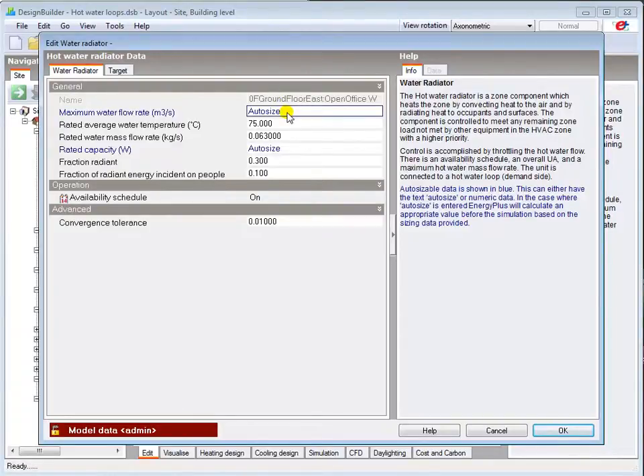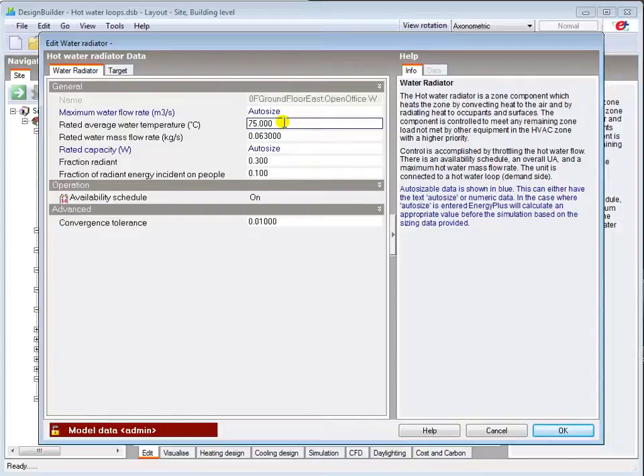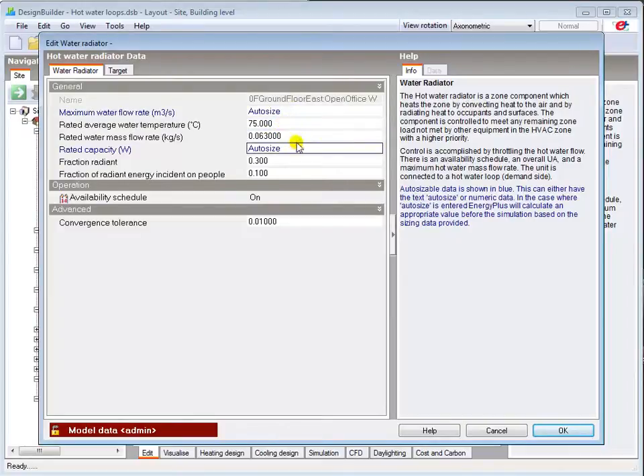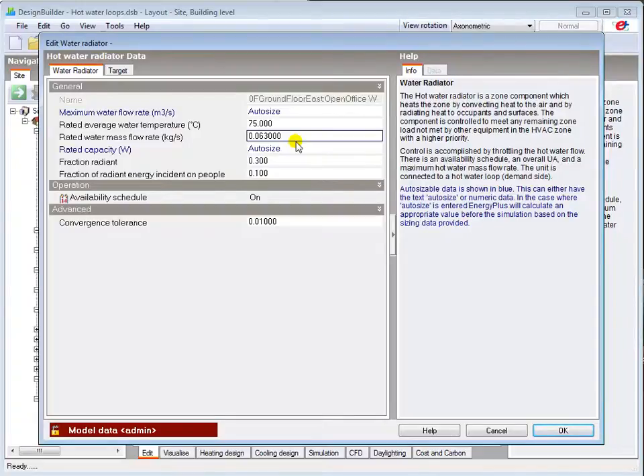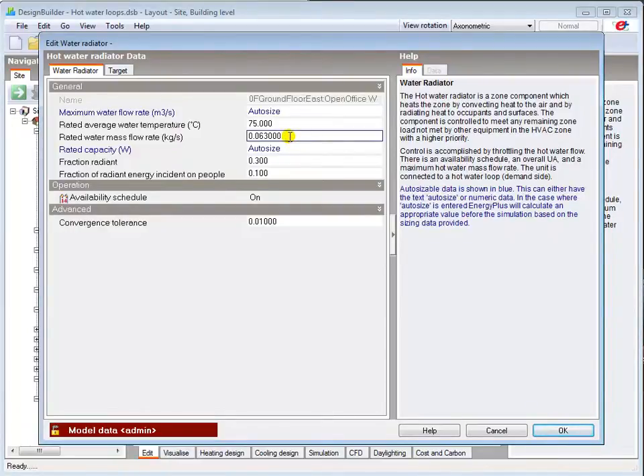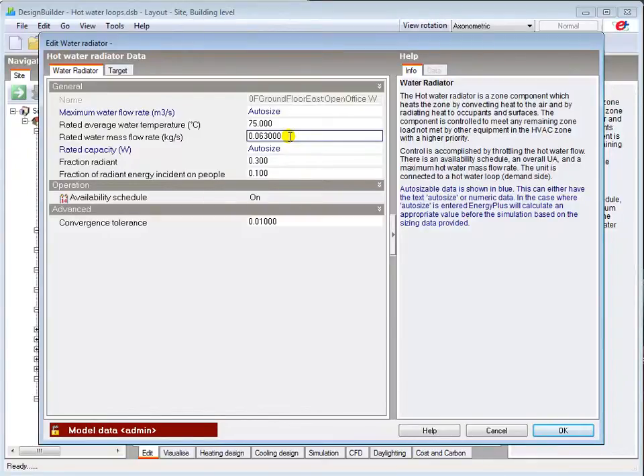The rated average between inlet and outlet water temperature, or mean water temperature, and rated mass flow are provided from manufacturer's literature, as they can be used to establish the performance criteria of the component. The default values are reasonable for traditional systems with higher flow temperatures in the absence of actual data, but not for condensing systems with lower flow temperatures.